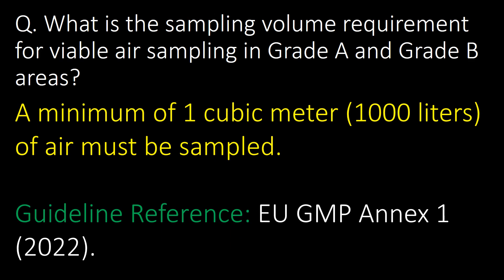What is the sampling volume requirement for viable air sampling in Grade A and Grade B areas? A minimum of 1 cubic meter, i.e. 1000 liters of air, must be sampled. Guideline reference: GMP Annex 1.